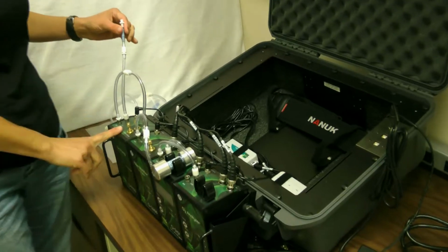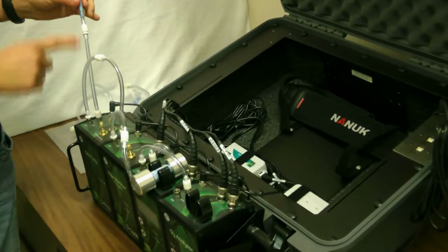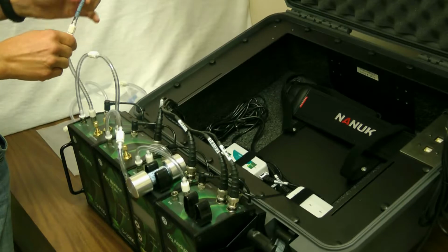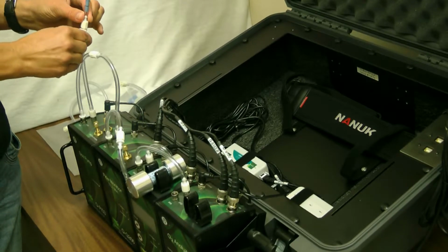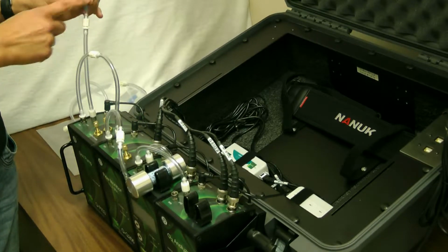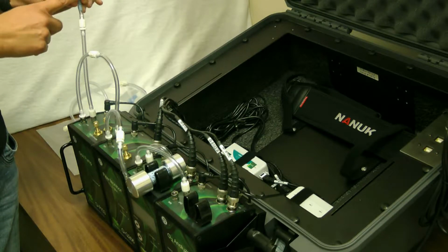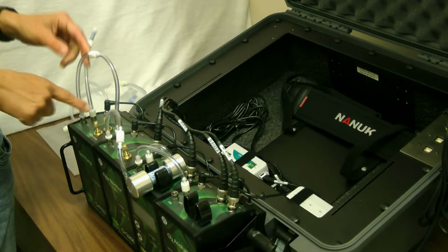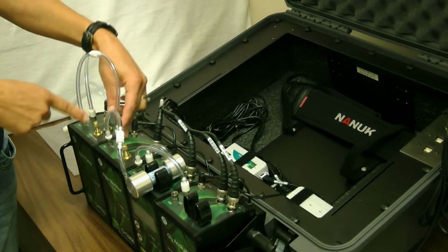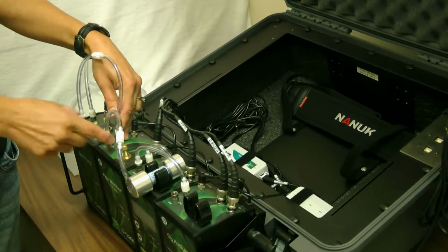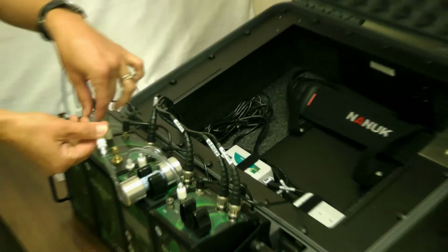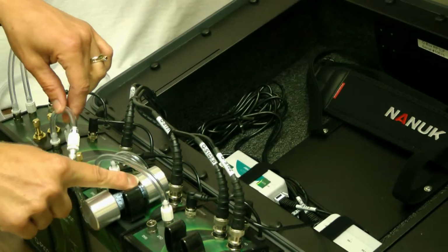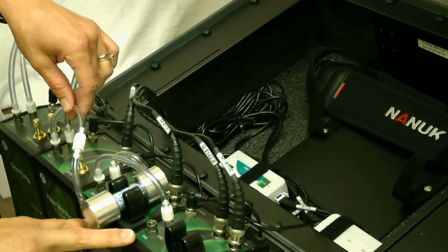You have a gas pump which is delivering gas to the system. There is a small inline filter which prevents any particulates from getting into the system. It should always be attached to the input of the gas pump. Then you have output of the gas pump going into the flow monitor. The output from the flow monitor is going through a drying column before it enters the two gas analyzers.